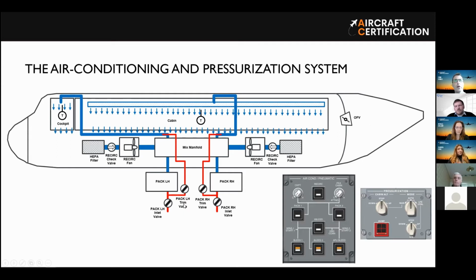So you have these valves here that are modulated by the AMS controller to reach the cabin temperature set points. In the cabin and cockpit, you have temperature sensors that are connected to the AMS controller. And in the cockpit, the pilot will regulate the temperature with these knobs here in the air conditioning panel. So here, for example, is the temperature control for the cockpit. Here it is positioned in the full cold condition, but it can be anywhere here. And in the aircraft panels, you have the digital reading of temperature sensors and additionally the set points. So the set points and temperature reading for each environment are shown in the multifunctional displays of the cockpit.